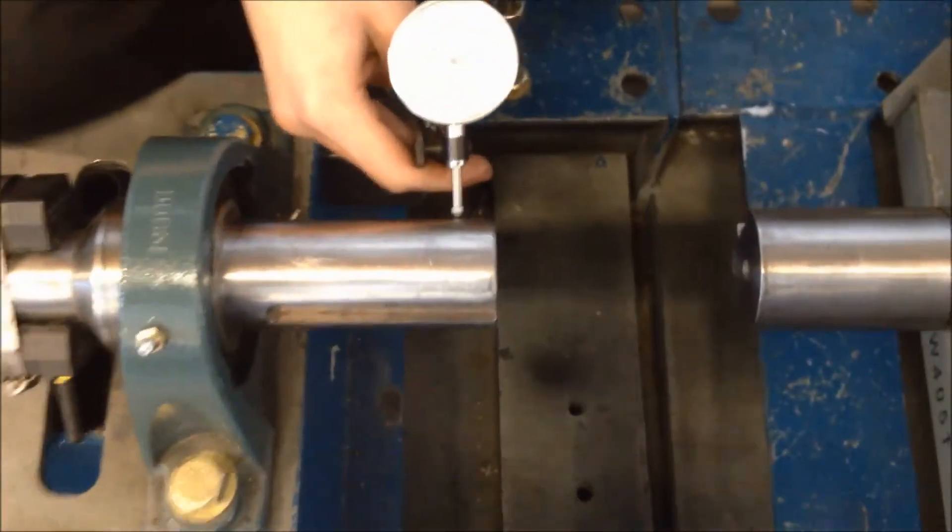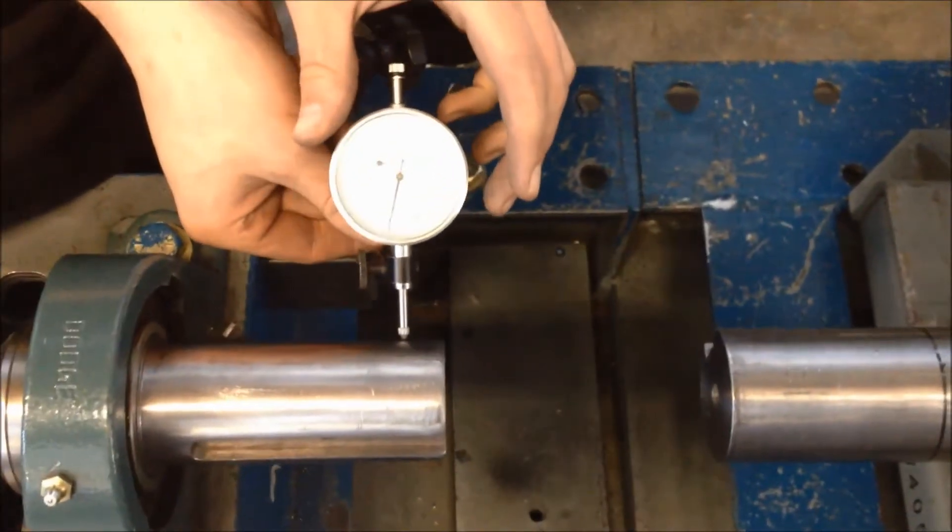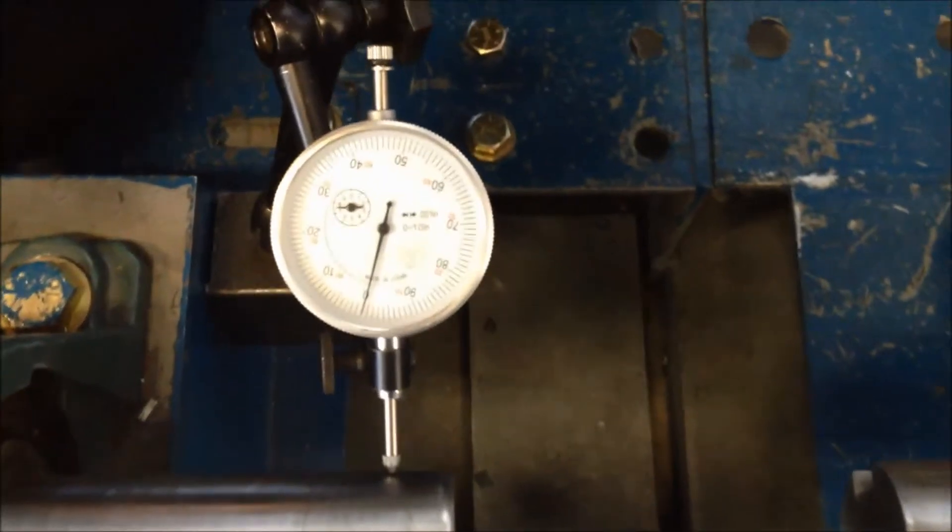Use a dial indicator to measure the shaft run out. Total indicator run out should not exceed 5 mils for 1,800 RPM applications and 3 mils for 3,600 RPM applications.